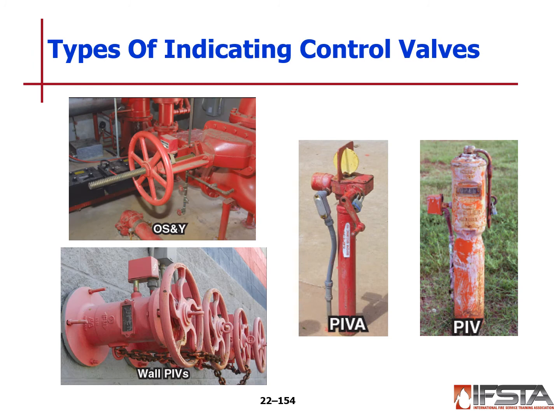Indicating valves could be the OS and Y, outside screw and yoke. Whether you see the threads of the screw part there or not tells you whether it's open or closed. The wall indicating valve, or wall PIV, has a window that has open or closed. The PIVA doesn't have an open or closed window, but it has the flapper on the top that tells you, according to which position it is in, whether it is open or closed. And then we have a post indicating valve, or PIV, that does have the window on it as well.